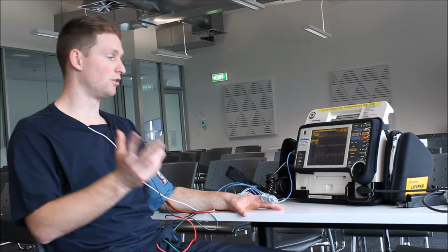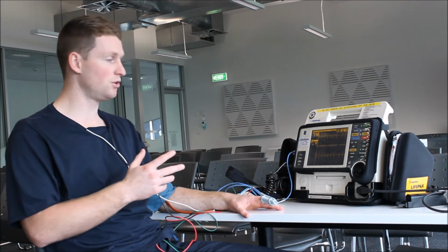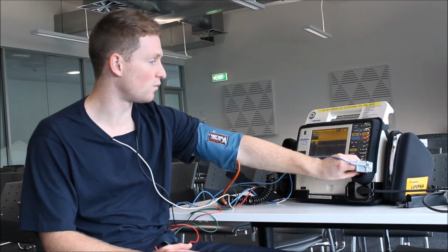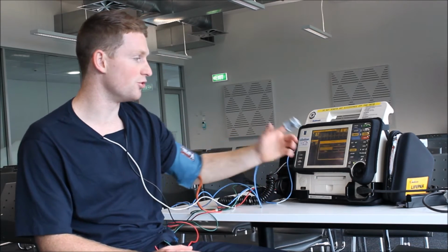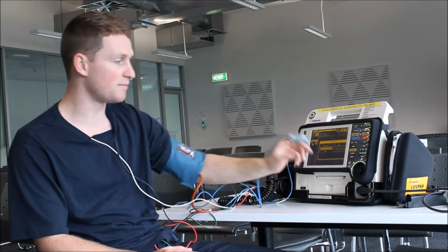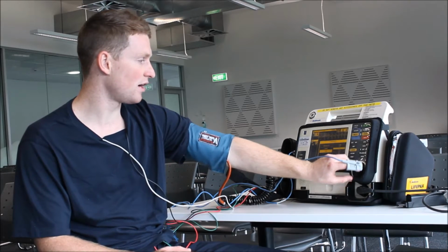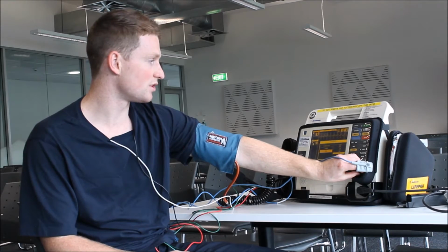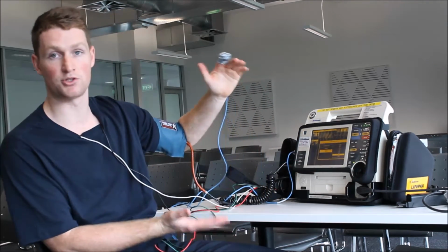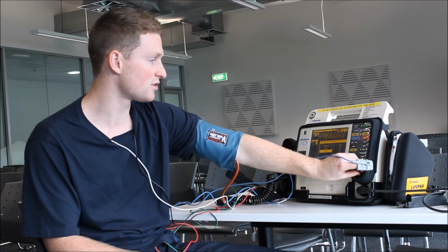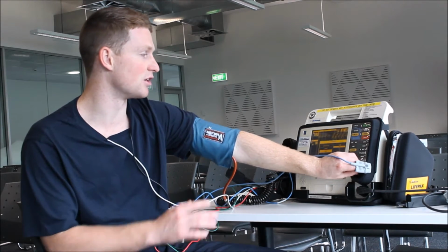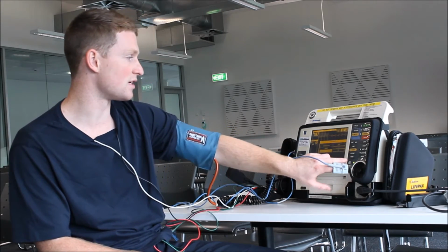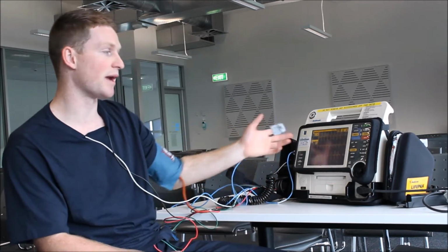Next, I'm going to look at the lead height, or amplitude. How I do that is use the selector knob again and go into one of the traces. Here we'll pick 1. Click the selector knob and it will show you different waveform, lead size and the type of lead. We go down into size, and then it'll give you a range of sizes. So you can go up, which as you can see makes the amplitude a lot bigger, maybe easier to see when it's quite faint, or if you want it less cluttered, go down to a bit smaller. We'll click 1.5, that's quite a good size, and then press the home screen again to take you back to the lead.